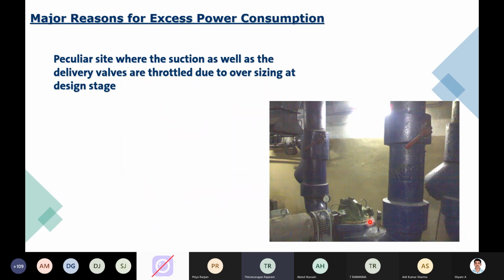So in terms of excess power consumption, this is one site wherein you could see a split case pump having a suction and discharge, and what we were able to identify here is that both your suction and discharge valves are being throttled. So meaning they have an oversized pump and are trying to throttle the situation and run it. Obviously, this will not help to have an efficient operation, and it also causes more service related issues on the product itself.